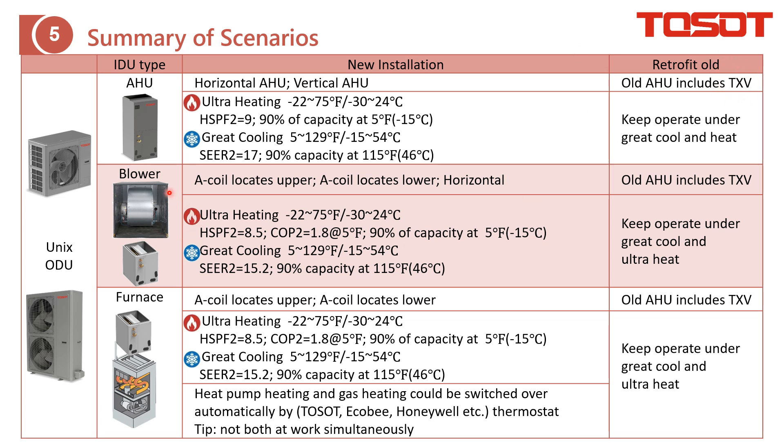The next scenario is unix together with a blower. In this case you will only apply an A-coil. The A-coil can be installed at the lower side or the upper side of the blower. With this setup you can also achieve ultra heating and great cooling. For a retrofit project, if the A-coil is not from Trane, it must include a TXV.